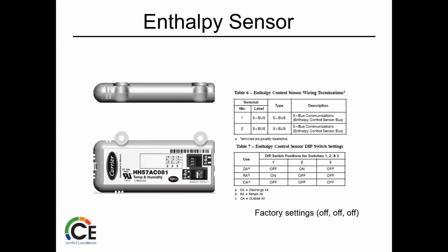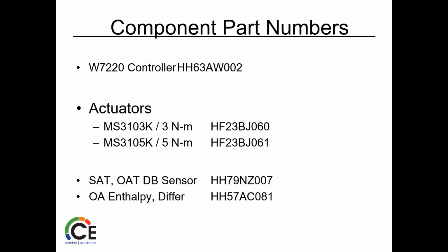There's that different enthalpy sensor. Again, you've got to tell it what you want it to be. Do you want it to be dry air, discharge air? Do you want it to be return air, outside air? The same control. You can have 3 of the same and they can all be something different. So they're all there waiting for you. The factory setting comes off, so it's factory set for outdoor air.